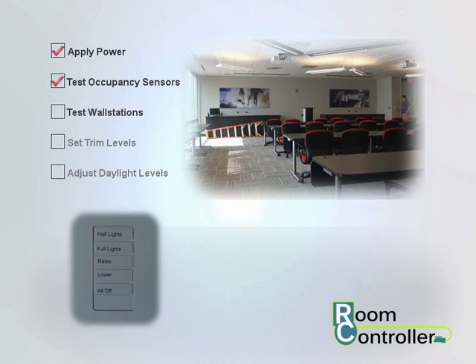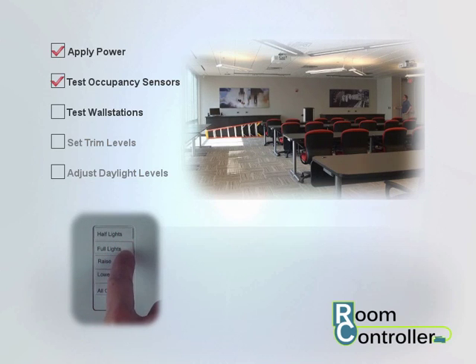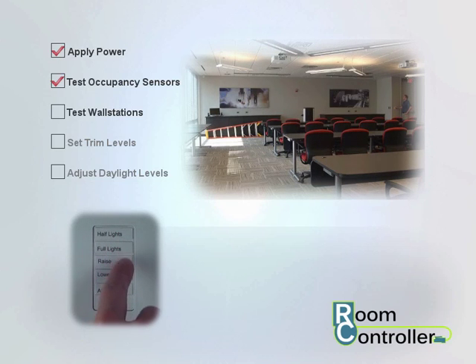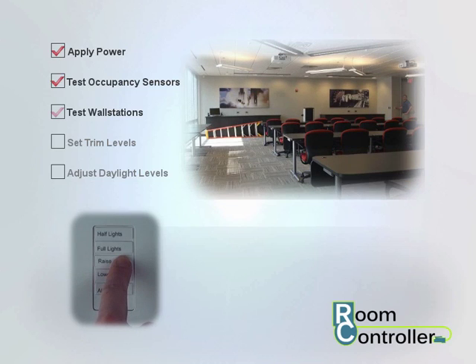Test each button on your wall station to verify it operates as described in the installation documents and controls the correct lighting loads and dimmer functions.